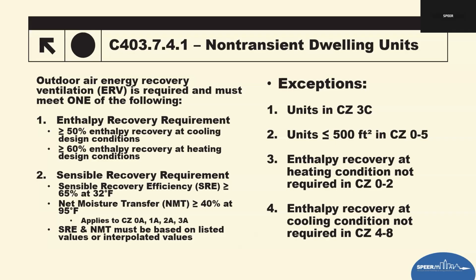ERVs reduce heating and cooling costs by transferring energy between the outgoing exhaust air and incoming outdoor air. That's kind of what an ERV will do. Option 1 basically requires the ERV systems to have at least 50% enthalpy recovery at cooling design conditions and 60% enthalpy recovery at heating design conditions. These values reflect the system's ability to exchange both heat and moisture. Then we've also got sensible recovery plus moisture transfer. That's the second path, and it does get more complex.